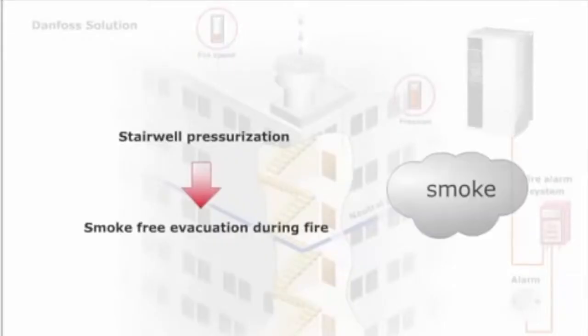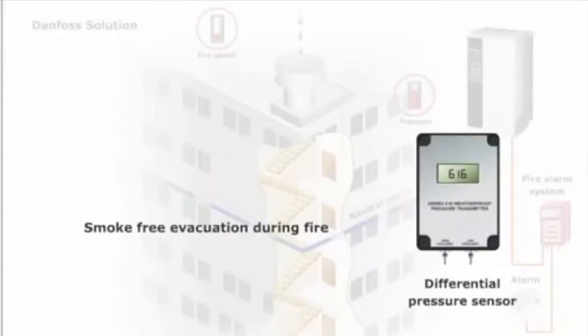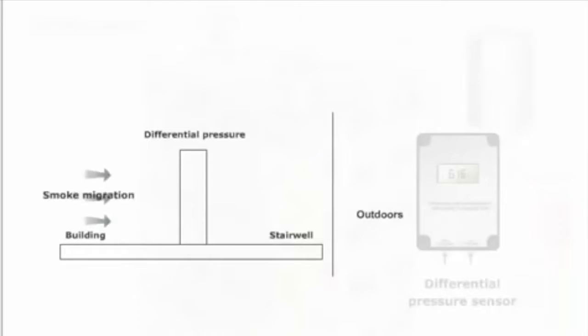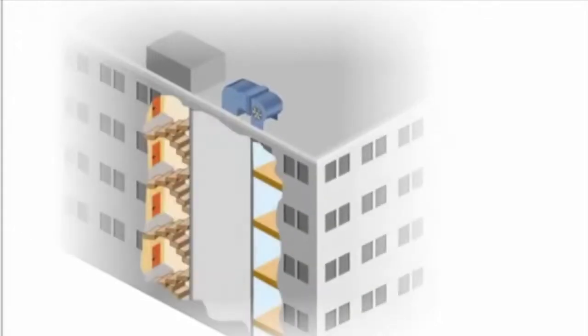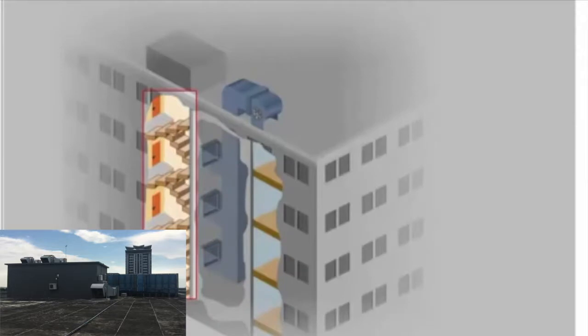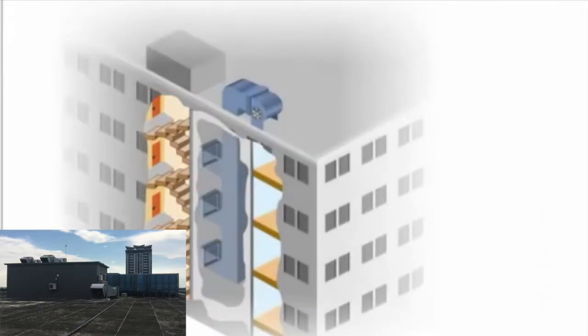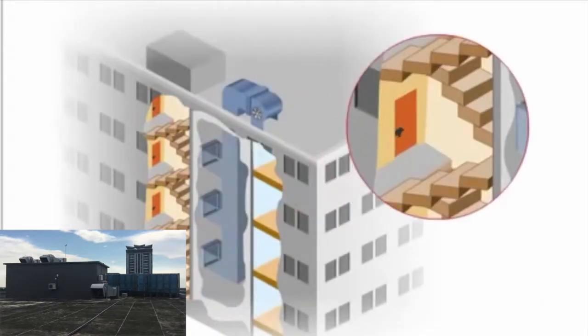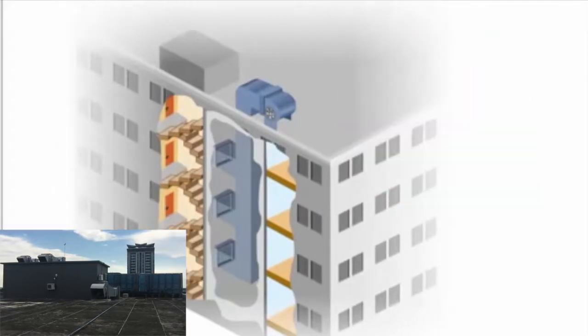Staircase pressurization serves as a smoke-free evacuation during a fire. Staircase pressurization uses a pressure difference across the door to control the movement of smoke to prevent smoke infiltration. Wisma Mustafa Kamal has stairwells that serve for routine building access and as emergency exits in the event of a fire. Airflow through the gaps around the door prevents smoke infiltration to the high pressure side.